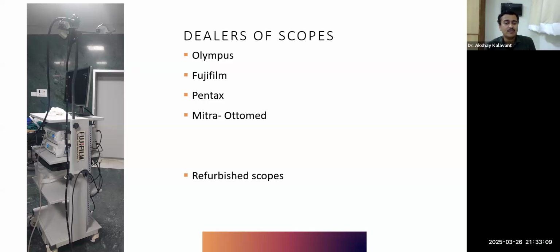Otherwise, it's not very much recommended, although you get these scopes for around 30% of the total cost of a new scope, because most commonly these scopes will have either issues with the camera, issues with the lighting system, or more often some leakages from the water channels or the air channels. Nonetheless, if your budget is very low, you can use this.